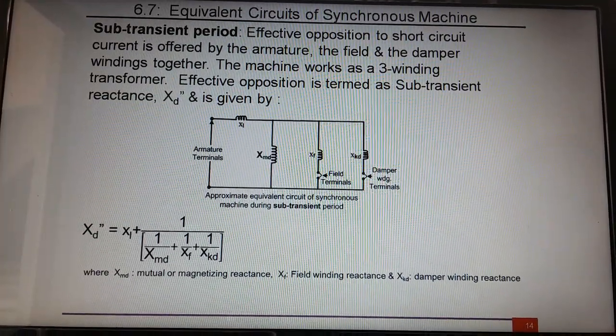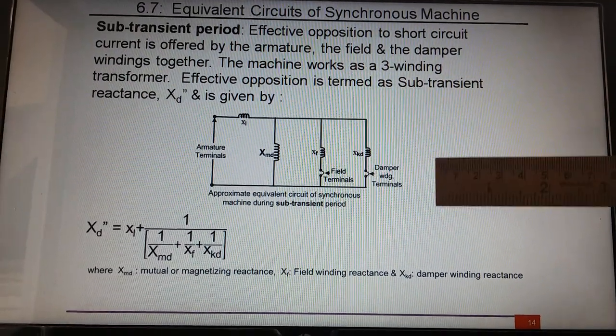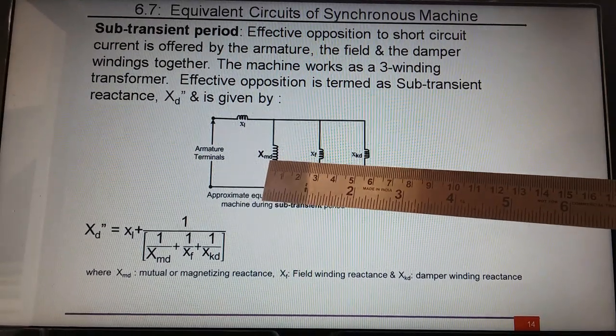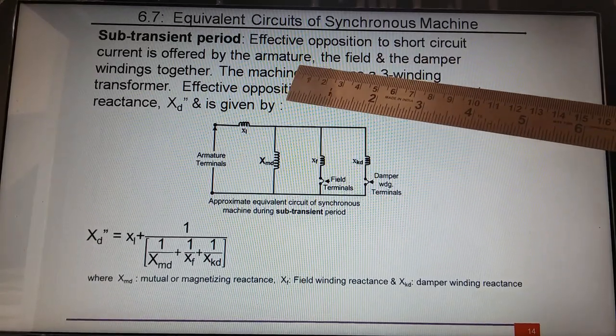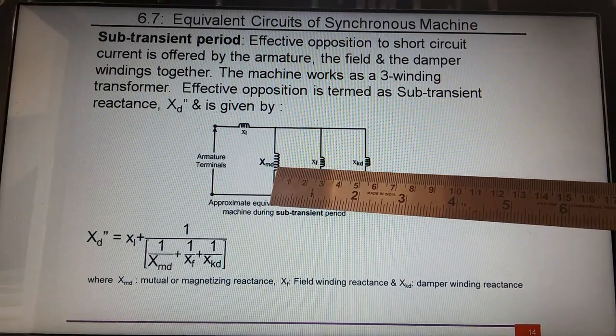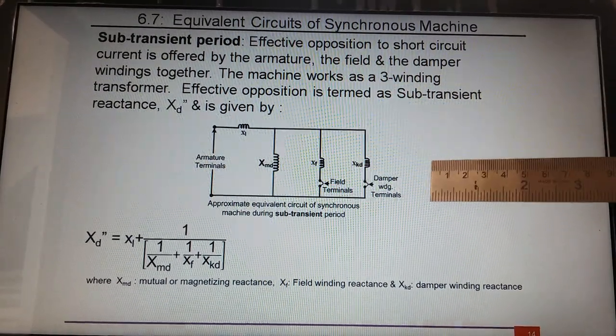The equivalent circuit displayed here is for when the alternator is suddenly short circuited. The conditions in the machine are those of a three-winding transformer, where the armature is the primary and the secondary consists of field winding and damper winding leakage reactance. The effective opposition to short circuit current is offered by XMD — the mutual reactance of the armature — along with the field winding and damper winding. The machine is working like a three-winding transformer, and the net reactance offered to the flow of short circuit current is what we are discussing.